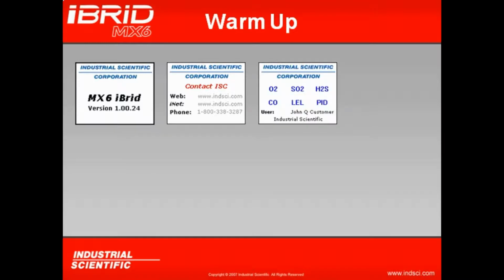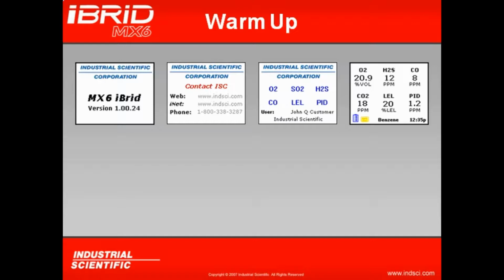The third screen that will come up will show us the sensors installed. With that, it may also show us user name and company name if so programmed into the instrument. And then that'll take us then to our real-time operation screen. Our real-time operation screen shows us the sensors installed along with the actual gas readings, but there are optional screens that may appear.